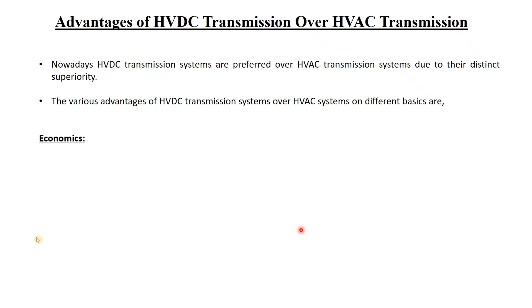Now, advantages of HVDC over HVAC. The first is economics. The cost of towers is greatly reduced, with less right of way cost and a simpler structure. I have already shown you that HVDC uses only 2 conductors, so the transmission tower has only 2 arms, but HVAC has 3 conductors, so 3 arms. So the cost of tower construction is also reduced, because we are using one conductor less.